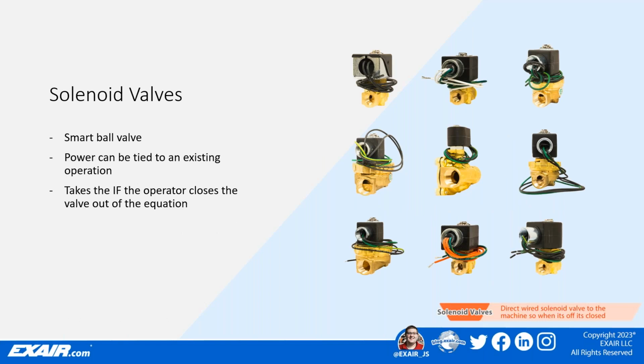Solenoid valves. For a more hands-off approach, you can have a solenoid valve that would tie into your existing PLC, e-stop circuit, or motor control to your compressed air line to aid in turning that compressed air on and off. Solenoid valves take that if your operator closes a valve out of the equation and leave you with the savings when the compressed air is turned off by the command you've chosen.